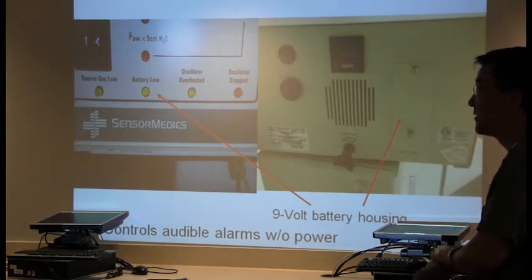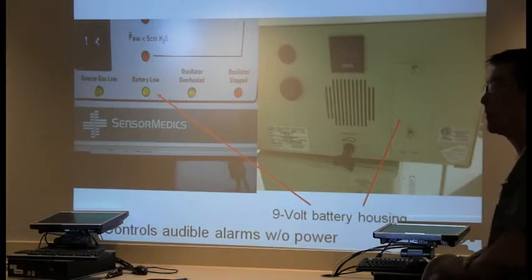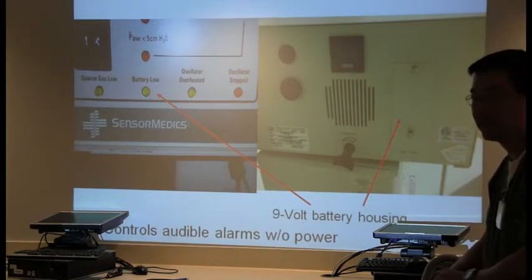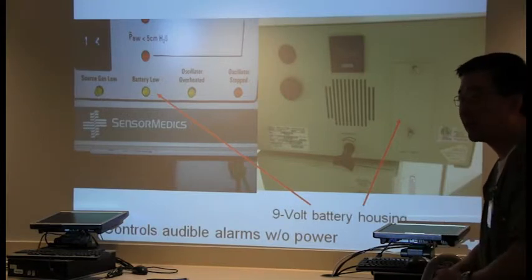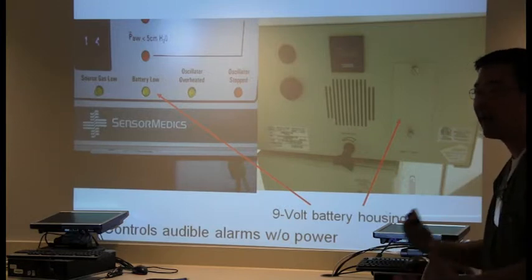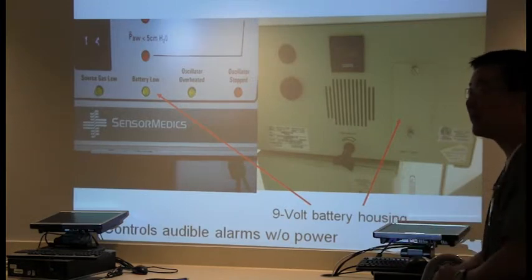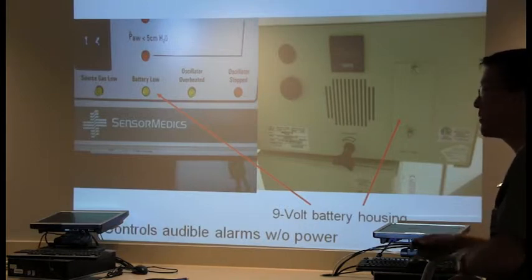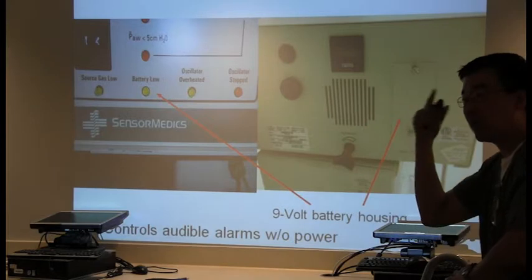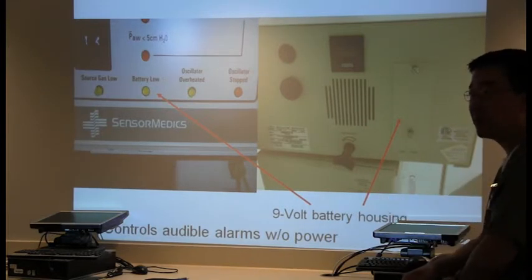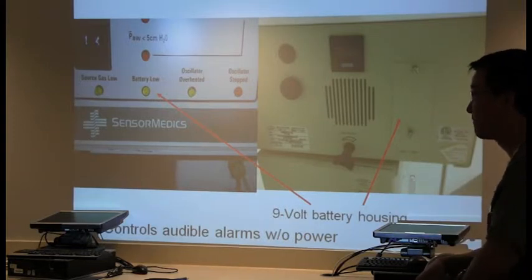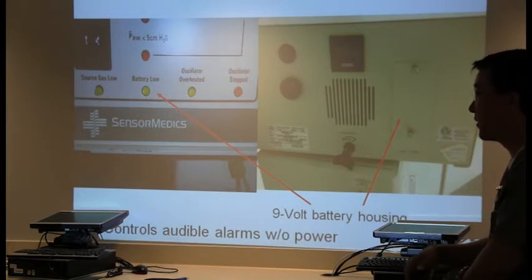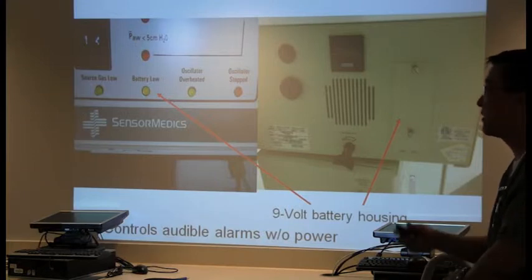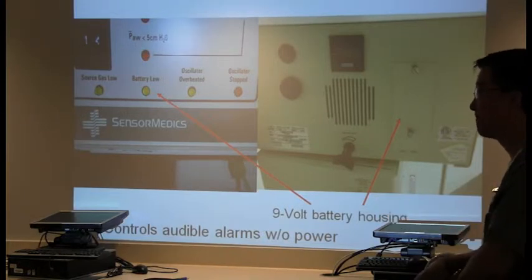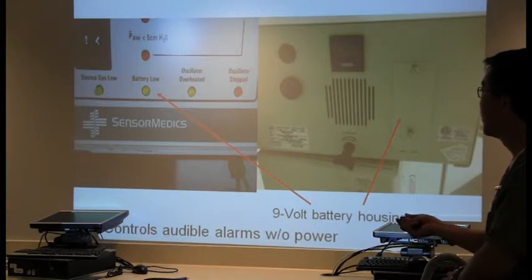Now, if this wasn't working properly, you would never know that the vent shut off, because the oscillator has no battery backup. It's such a huge, powerful machine that there's no battery to back it up like the Avea and the A40s. That's why it's very important that you monitor this alarm. So when the ventilator loses power, this thing will alarm. Chirp, chirp, chirp, chirp, chirp. Annoying alarm. That's all that means. Even though it lights up when the ventilator is powered and working great, ultimately, when you lose power, this is what's going to save you. Oscillator overheated.